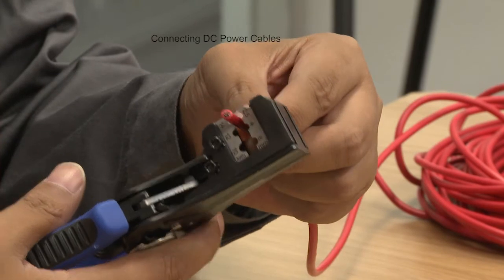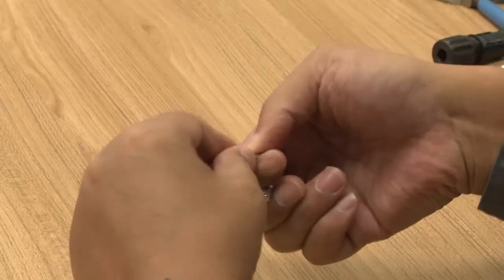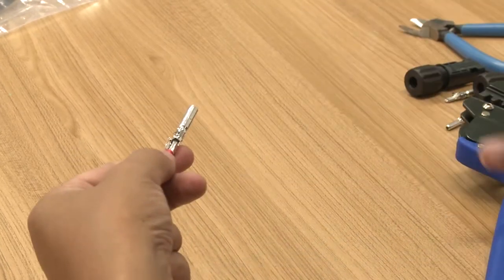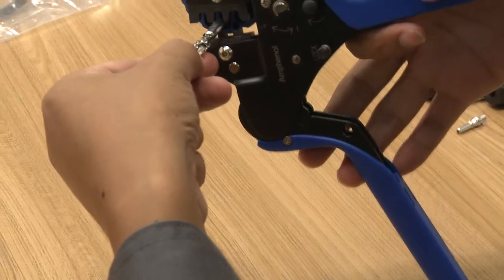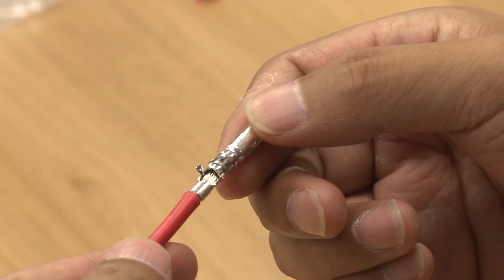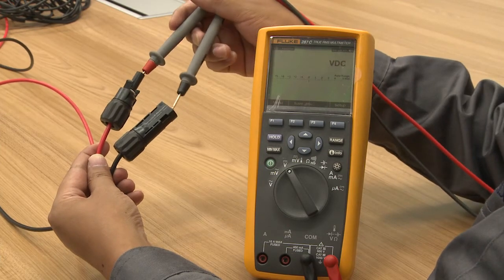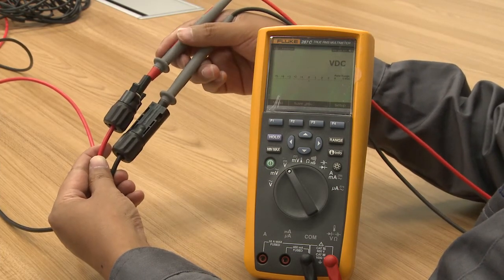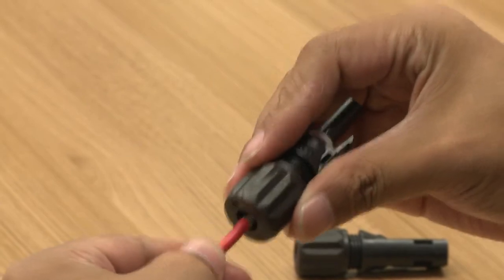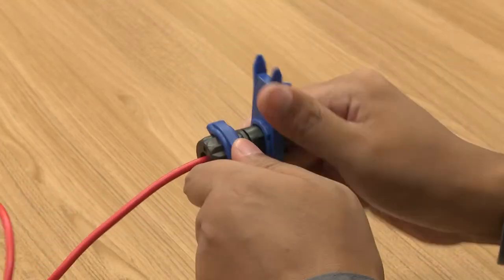Remove an appropriate length of the insulation layer from the wires of the DC input power cable using a wire stripper. Insert the exposed areas of the DC input cable wires into the metal terminals of the positive and negative connectors respectively, and crimp them using the crimping pliers. Measure the voltage with a multimeter to ensure that the voltage of all DC terminals is within the normal range. Insert the crimped positive and negative power cables into the corresponding positive and negative connectors. Tighten the waterproof nuts using the tightening tool.